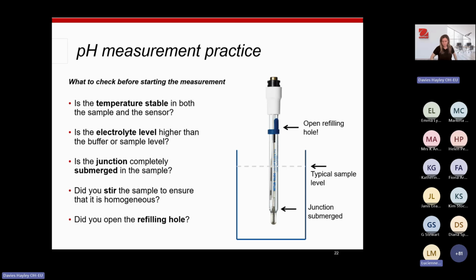Wendy, if you can put a little message in the chat. Yeah. So the reason mold may be forming is it's sitting in old electrolyte storage solution. We mentioned replacing the electrolyte storage solution once a month, and this is for reasons like this. The solution can get contaminated, it can get dirty, bacteria can grow in there, and it can cause molds and all sorts of other nasty things. So that's why it's recommended that you change the storage solution at least once a month, which I know in certain circumstances can be quite difficult to do.